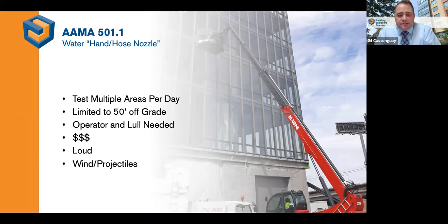Some pros and cons: you can test multiple areas per day with this type of test method. A limitation is it's limited to about 50 feet off the ground. I actually didn't know that when I lined up the testing agency for this test, and some of these areas were up higher, well over 50 feet. We lucked out, and I'll show you how - it was a mezzanine we were able to work off of. But if you're specifying this test, confirm with your testing agency what the height limitation is. It's actually not based off the lull, it's based off the tether they run the fan off of, so just be aware of that.